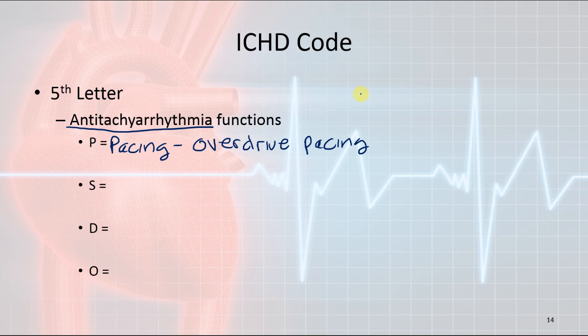It's called overdrive pacing. S is for shock, which is actually for any kind of implantable cardioverter defibrillator. So that's usually the implantable cardioverter defibrillator of a patient who goes maybe into VTAC. If you have a patient that goes into VTAC, it will shock the patient. D is set for dual, which would be weird, to set it to overdrive pace and to defibrillate, but I guess some people's hearts are that bad. And of course, O is set to none.